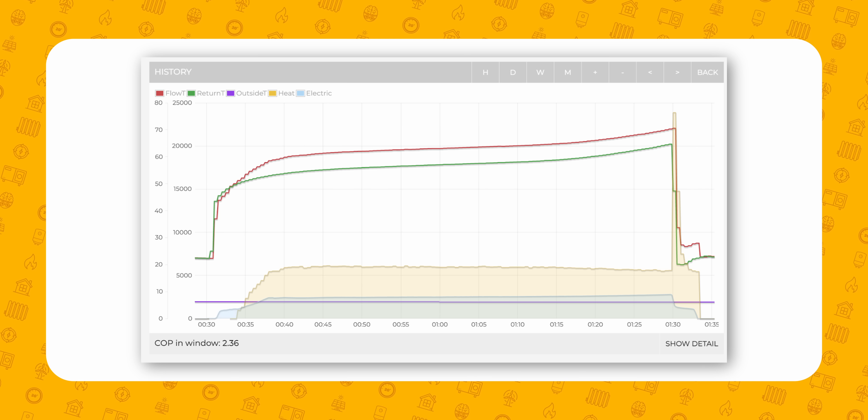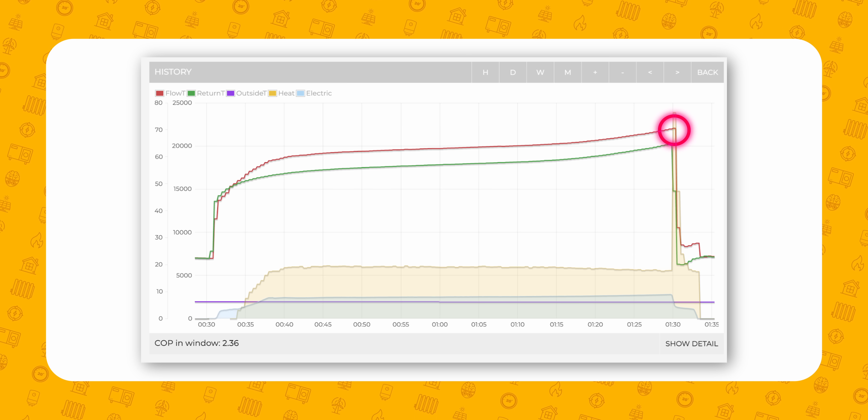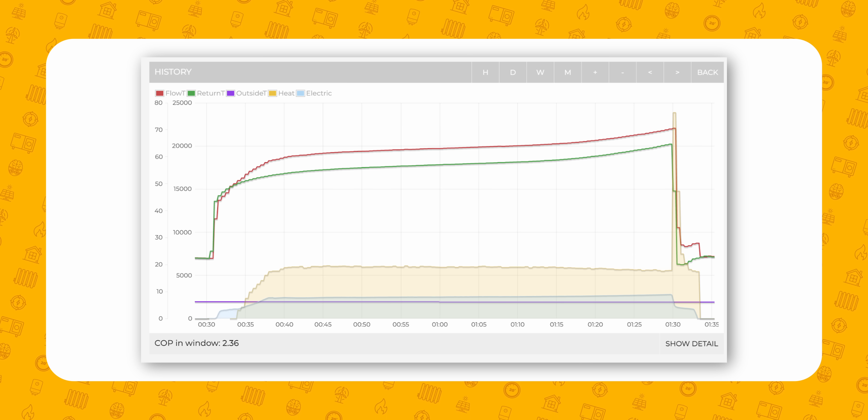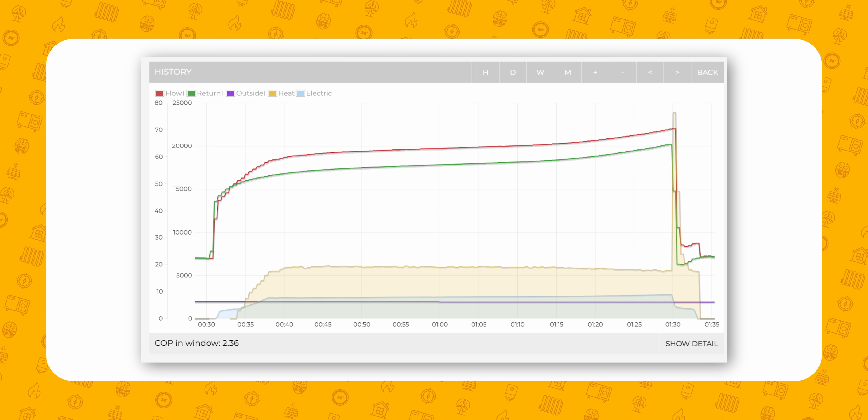The Sunamp additionally doesn't tell the heat pump what the store temperature is. It instead uses the same resistor switch that Mixergy uses — there's a link to the Mixergy video in the description. Just to be clear, the heat pump may not actually reach its full set temperature, but by having advanced controls, you can hold back your heat pump more and maintain longer at lower temperatures. We have a couple of Sunamps we're monitoring, and as you can see here, the flow temperatures required for heating the system up reach up to 70 degrees Celsius to heat the hot water, which isn't great for SCOP. Here it only has 236% efficiency and will probably average under 250% efficiency for the full year.